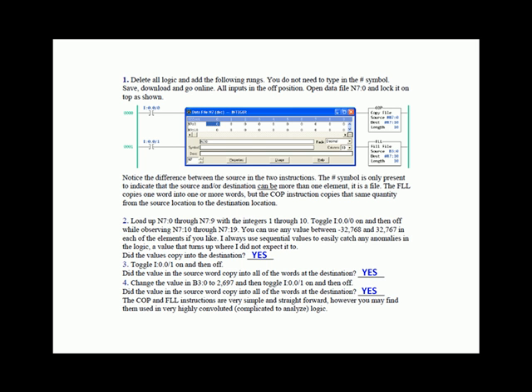It's real typical when tracking the position of cartons on a conveyor to have a pulse generation that triggers a copy file instruction to copy a group of words that represent the length of the conveyor to one word higher in memory, and keep doing that so I keep shifting the values up through memory to represent the cartons by product code moving on the conveyor.